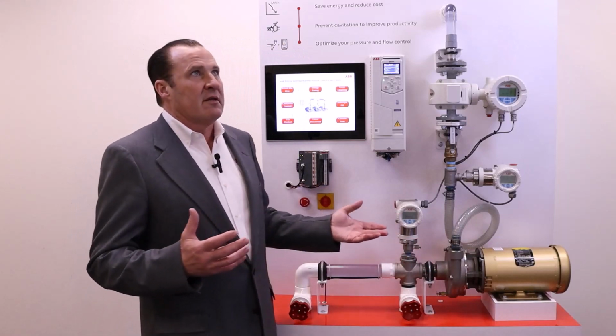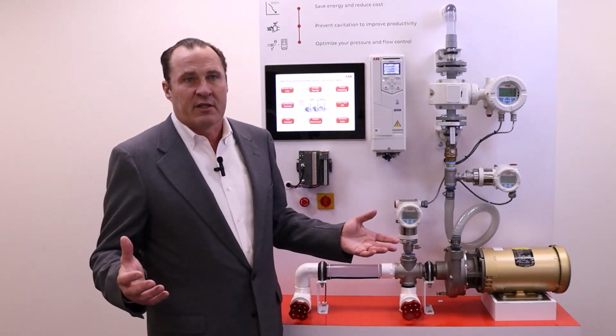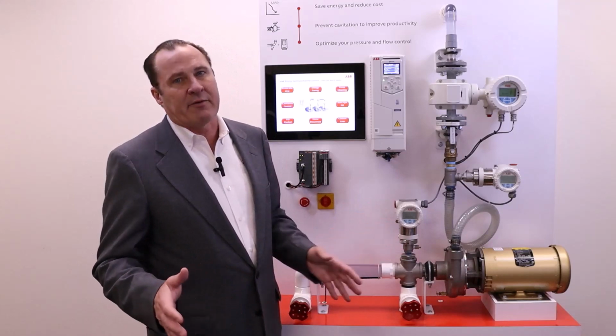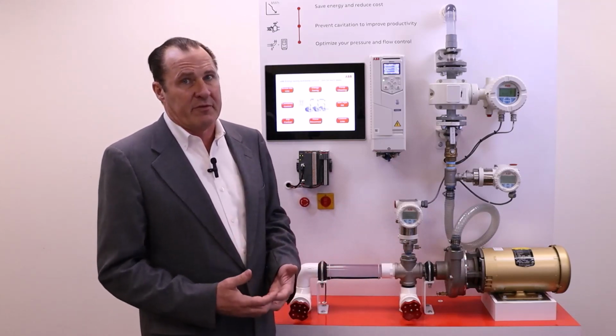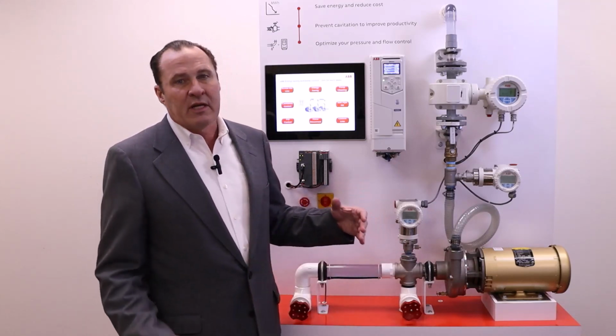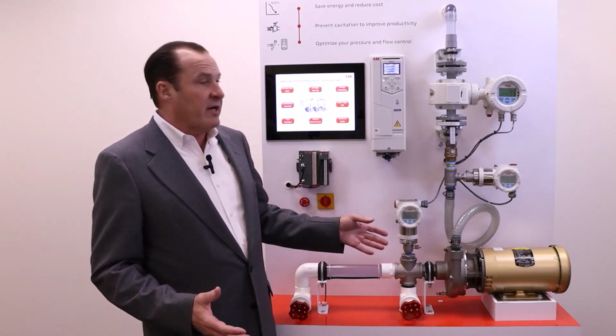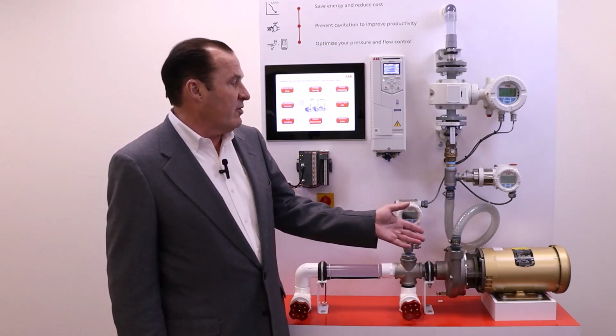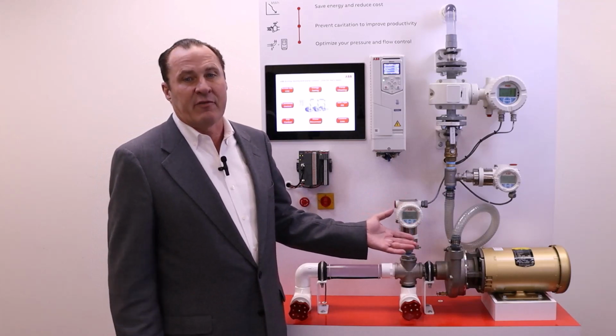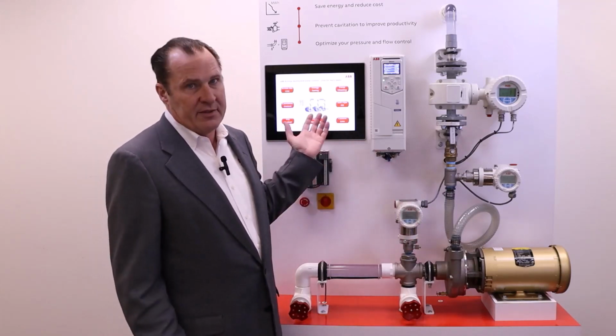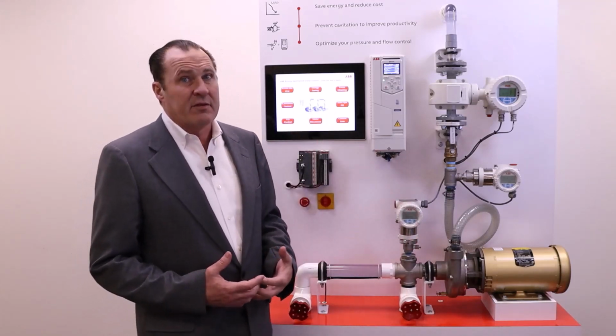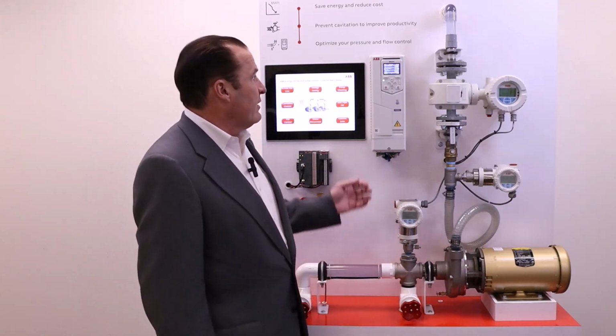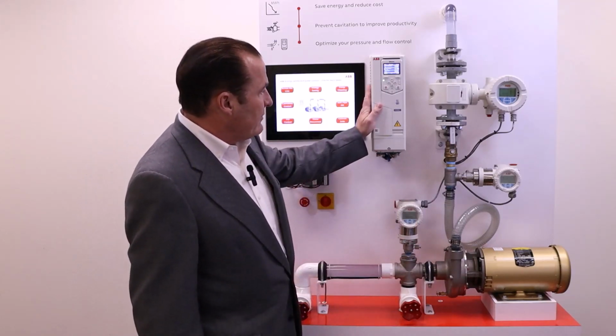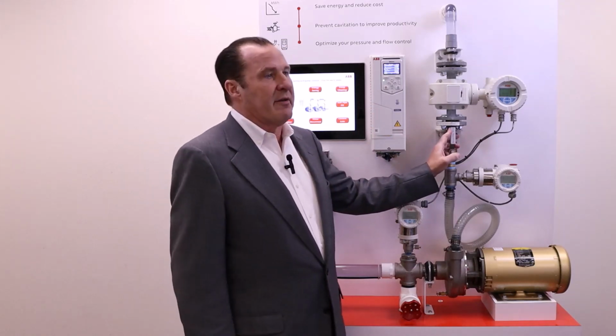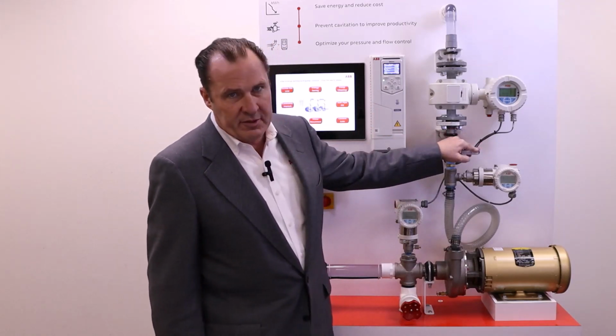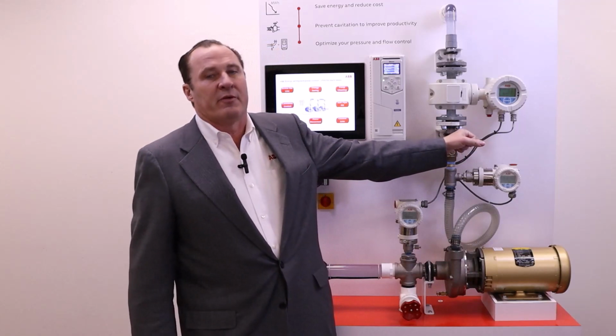Simply taking some pump charts and trying to figure all this out won't be accurate enough to have accurate sensorless pumping flow. In this case here, we're going to have a limited range of what this pump will actually run at. It's actually a 2 horsepower motor, but I can only get about a half horsepower of total loading on this system. But for what we're going to do, this will work out just fine. We got our drive, and we got our throttling valve.